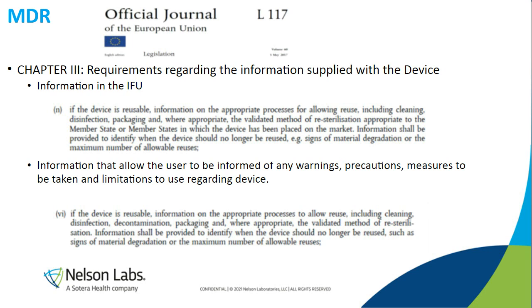There's an "or" there. So if you read between the lines, the MDR does allow that, as long as you have written in your IFU how the users or processing personnel can identify degradation, or how the device is no longer usable, you may not have to perform these cycles.